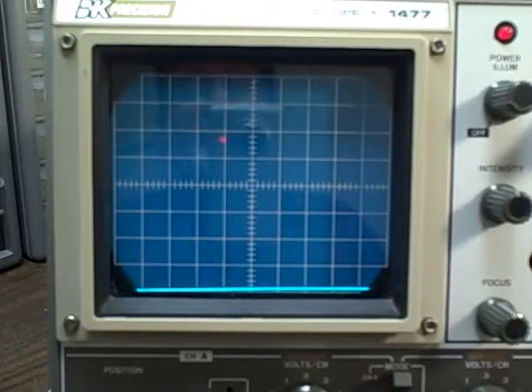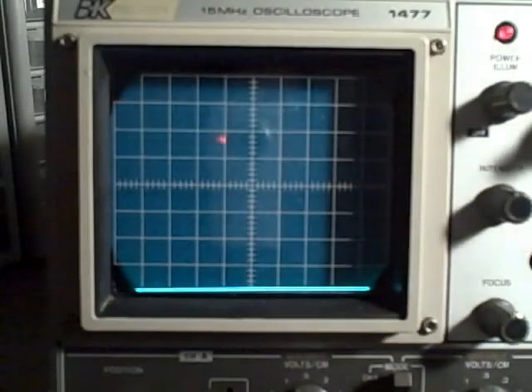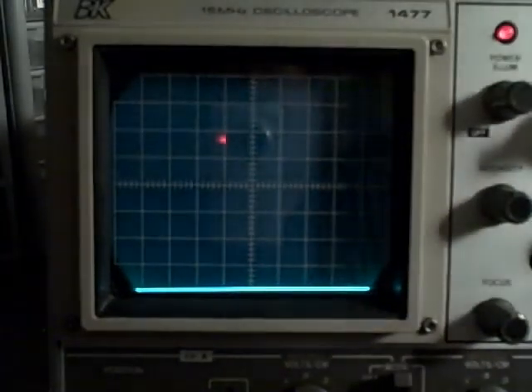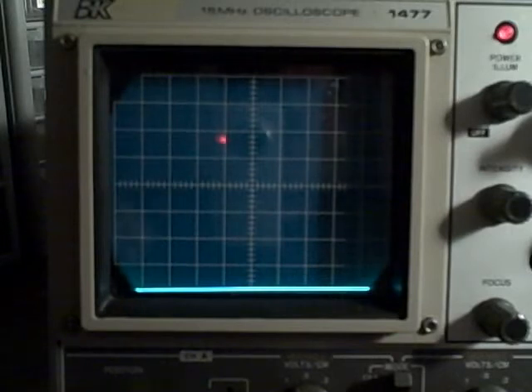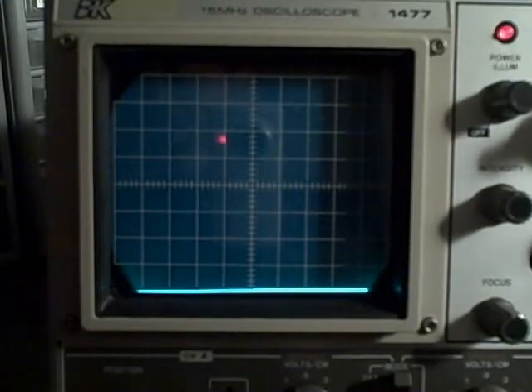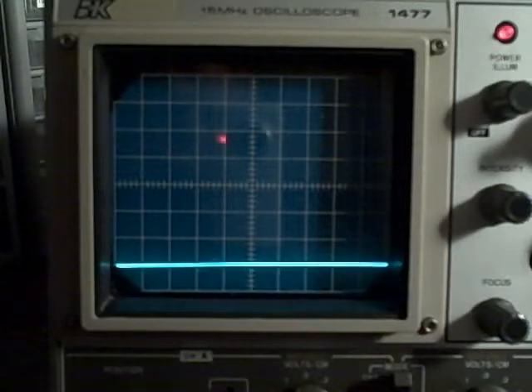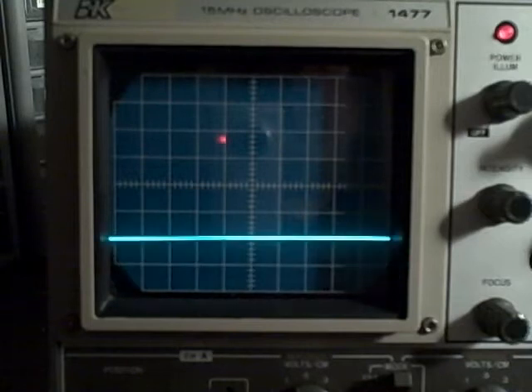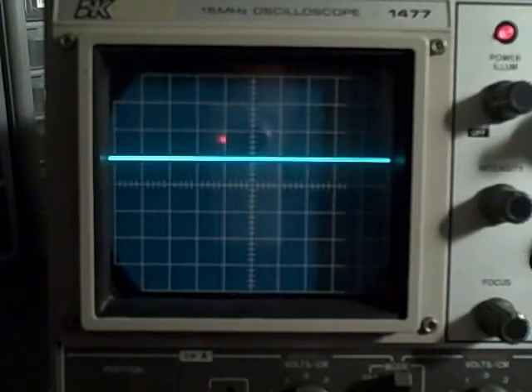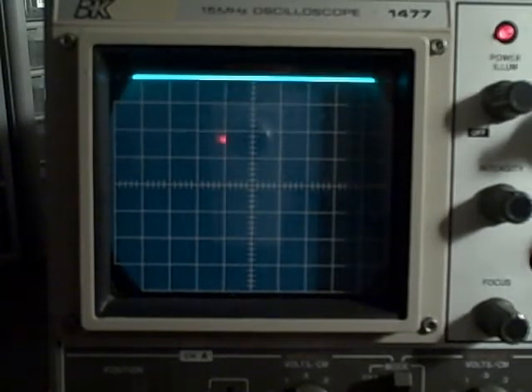Okay, we're going to go ahead and check the vertical linearity of the scope on channels A and B. Right now we're on A. We're going to be applying DC voltages and observing the trace as it moves up the screen to see if it represents the appropriate voltage with a number of divisions on that range. So I'm going to turn off the light to get a little better view of the screen. Hopefully a little less glare. Let's try that. Okay. Right now we're on the 0.01 volt per division, and we're going to try and step up one division at a time. One step at a time. One. This would be 0.01, 0.02, 0.03, 0.04, 5, 6, 7, 0.08 volts. Perfect every step.